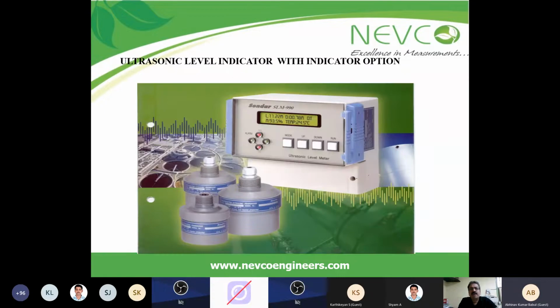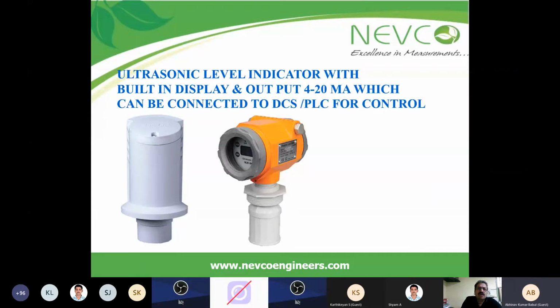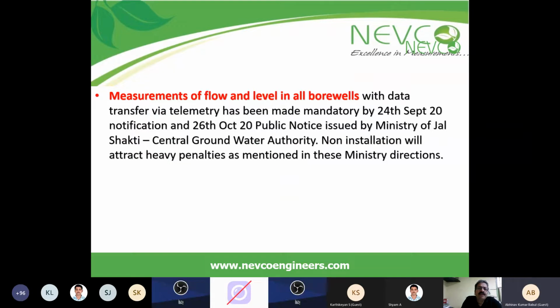Then we have the ultrasonic level indicator, for level indication in a tank, in a pipe, or in any liquid application, water application, or storage application - applicable for various uses. This ultrasonic level indicator, with or without display, has a 4-20 output which you can take to a PLC or DCS in a control room to know the exact height of the liquid.